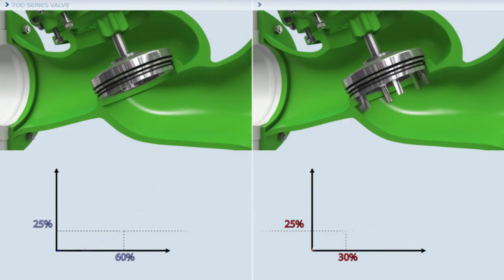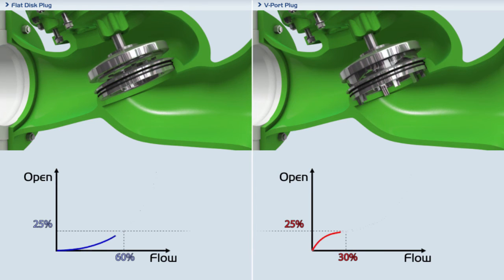The V-port plug changes the ratio of flow to stem travel, making the stem travel longer than the flat disc for the same flow.